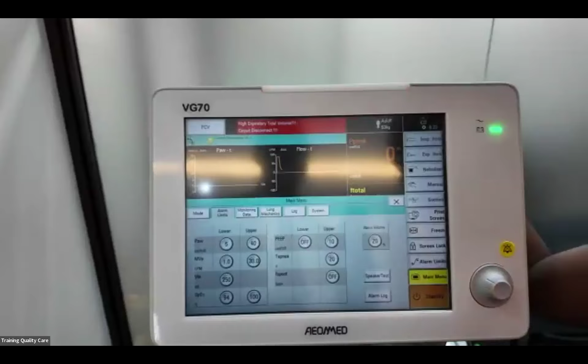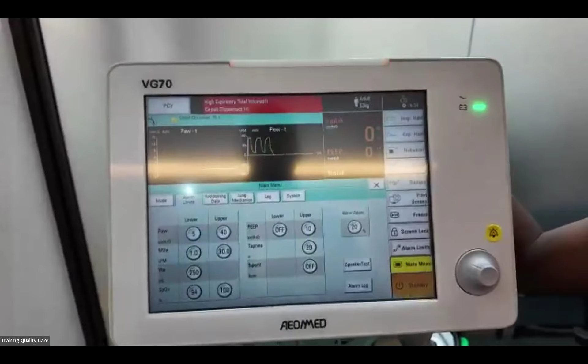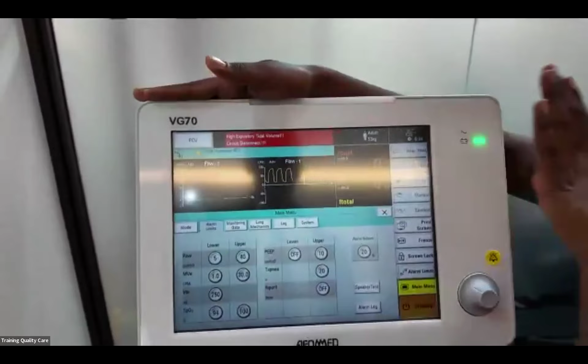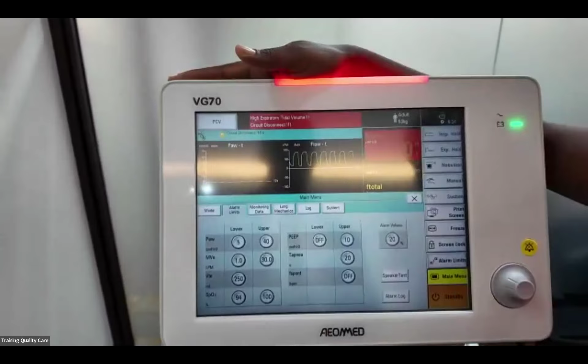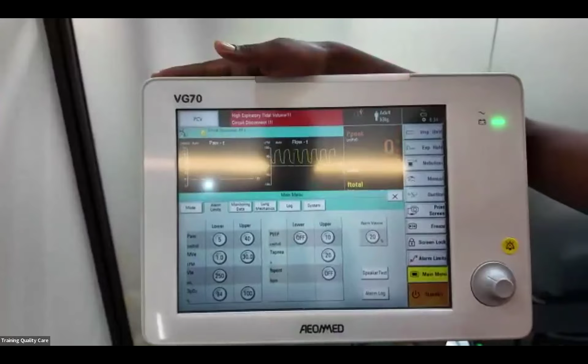Now, the other setting that I need to talk about is the alarms. And alarms, or the limit, is what limit do I want to set on this patient, so that in case it goes higher or it goes lower, the ventilator alarms and alerts me I need to check on the patient. So things that we set is something like the pressure. What is the lowest pressure? That is the peak inspiratory pressure, the pressure on the airways. What should be the lowest and what should be the highest?